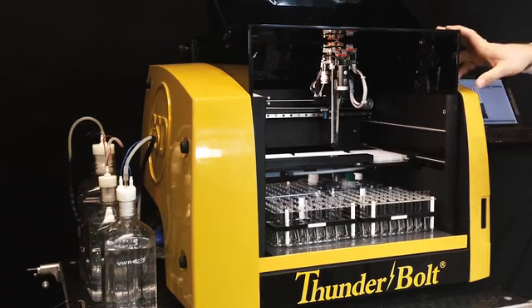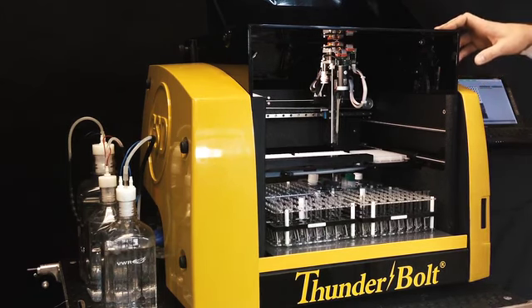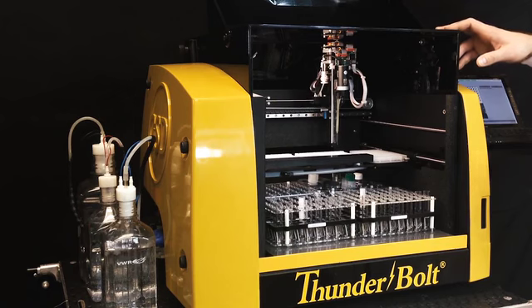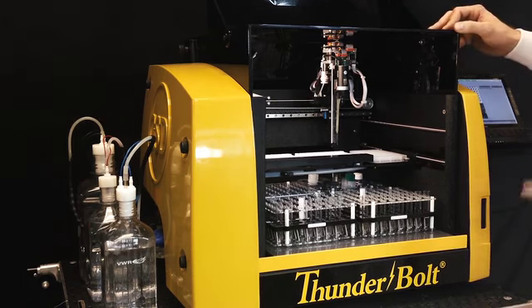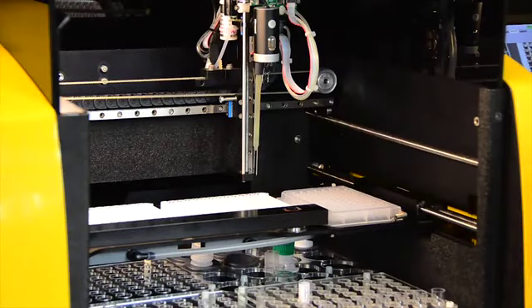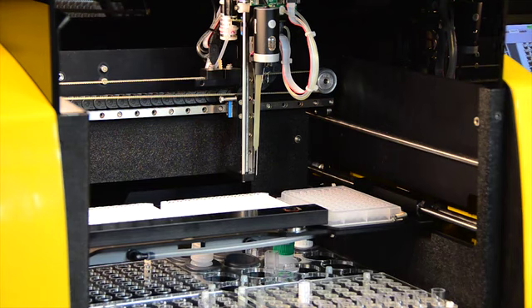Now the probe is a single probe dual needle system. Now you might wonder, well, how then do you wash the plate? Well, the answer is that we wash the plate using that same probe. Now the single probe system, yes, it means that we will have to then wash with that same single probe, but we have chosen to do that on purpose. And the reason is that we can then treat every well identically.